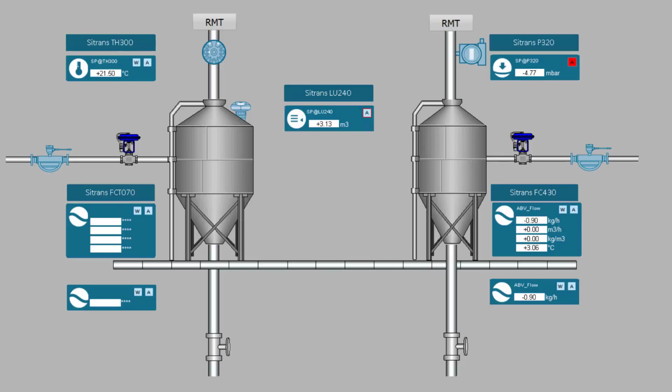So this is my WinCC runtime, and the reason I'm showing this, you'll see the data here, you can see the flow meter values flipping around, and that data is what we class as cyclic data. So the PLC is communicating to the instrument with the aid of having a GSD programmed into the PLC, so it knows where the data is on the device. PDM maintenance station will not affect the flow of this data because it communicates acyclically. Okay, so that's the first tick in the box. We're not going to affect the main flow of data into our control system.